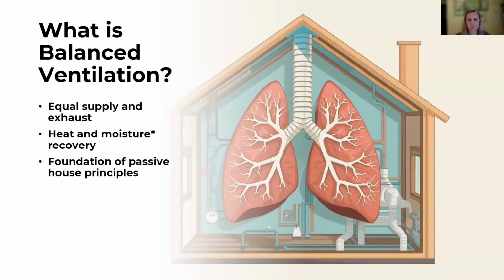What is balanced ventilation? I was always told balanced ventilation is the lungs of the building, hence the graphic. Balanced ventilation means supply and exhaust airflows are equal, so the building stays pressure neutral. Supply zones, or rooms where you'd see supply air going in, are typically living rooms, bedrooms, and offices. Extract or return air rooms would be your kitchen, bathrooms, and laundry, to get rid of moisture, humidity, pollutants, and stale air.